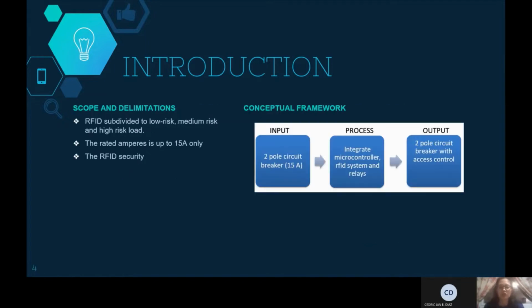For the scope and the limitations, RFID is subdivided to low risk, medium risk, and high risk load. The low risk is for the technician. Medium risk and low risk can be controlled by the supervisor, while the manager can control low risk, medium risk, and at the same time high risk. The rated current is up to 15 amperes only. The system was set at 12 amperes or greater, and it will be considered an overcurrent once that is met. And then lastly, for the RFID security, there are circumstances where RFID cards are cloned, so that is not in the scope of the study.